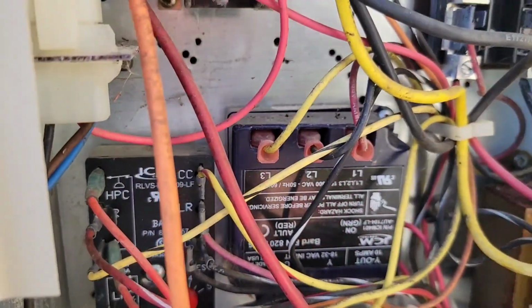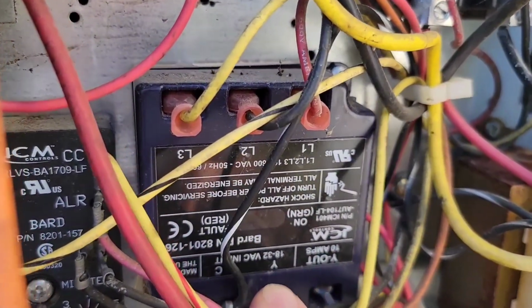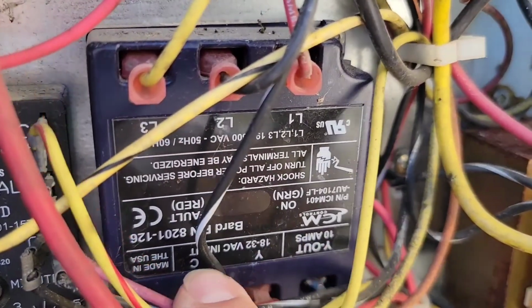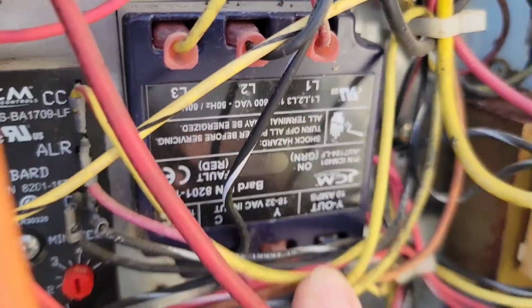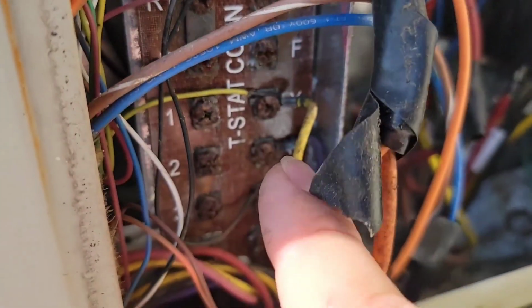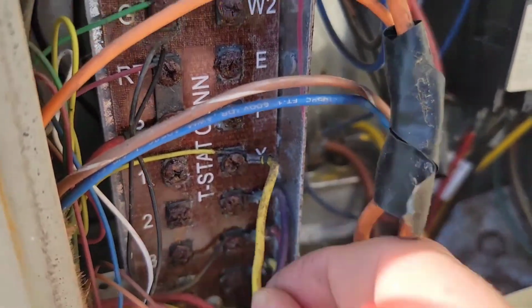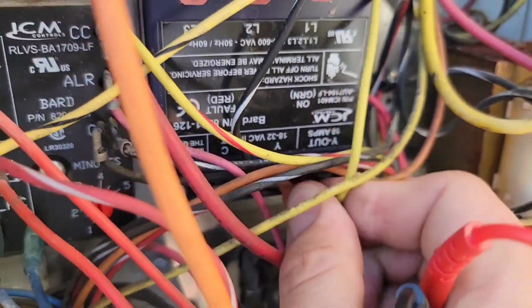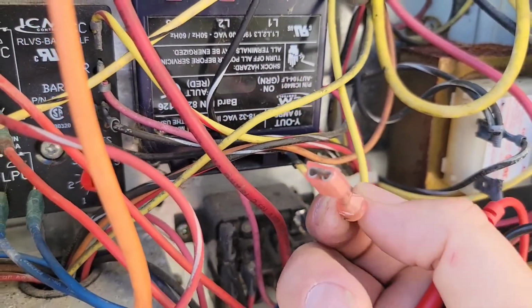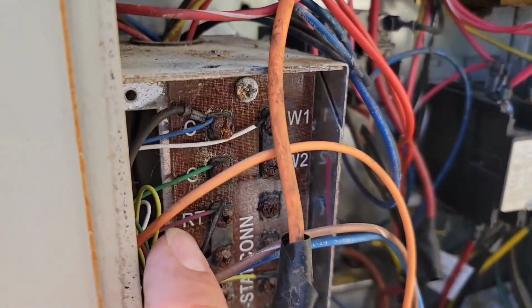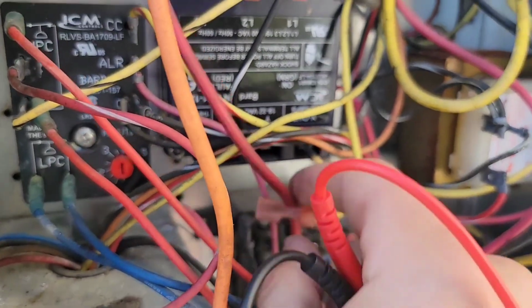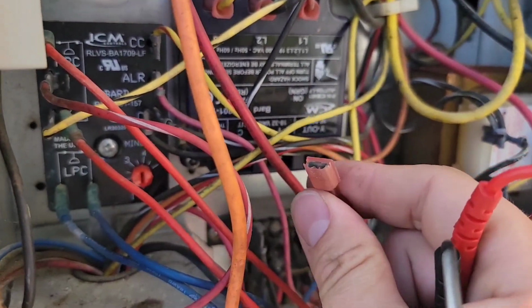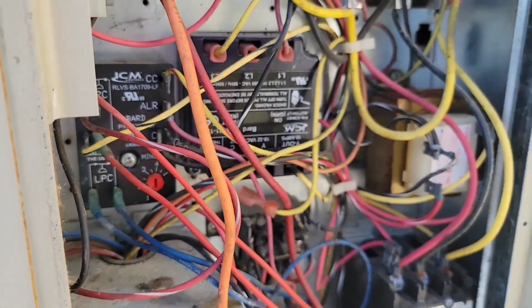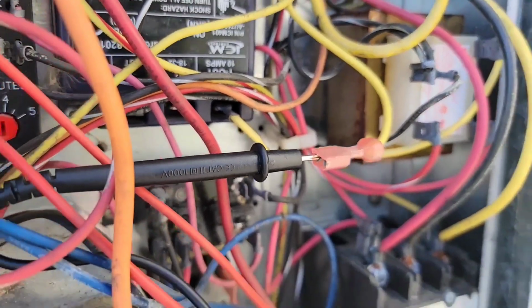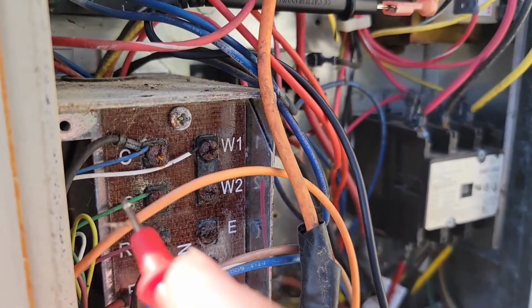Okay, so this is the phase monitor right here. It monitors the phases. It's the safety control. And we got C and Y. So from this Y here, this wire goes into the phase monitor right here, okay? So if we take this wire out and measure from this C right here to this wire, we should have 24 volts going into the phase monitor. Let's do that now. Okay, so I am measuring from that Y.